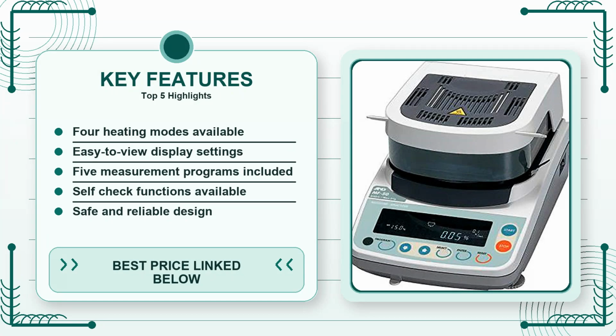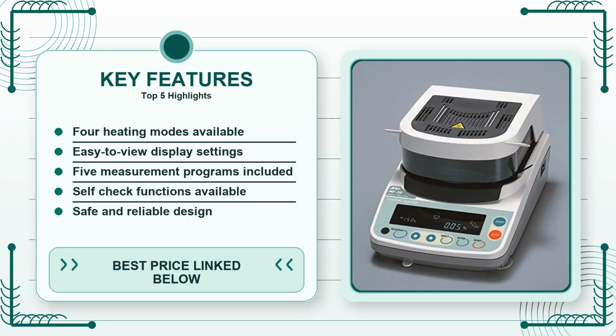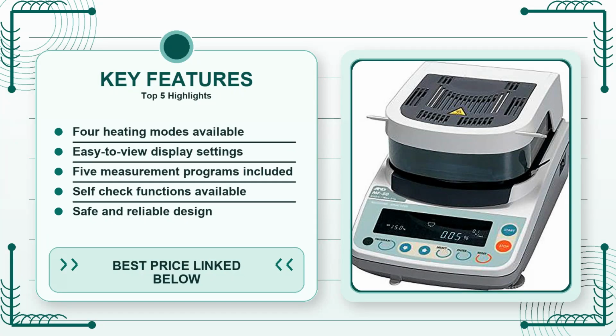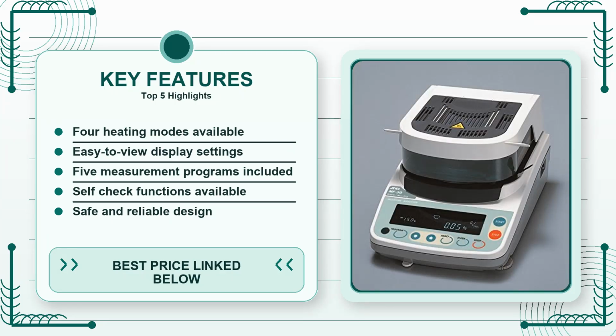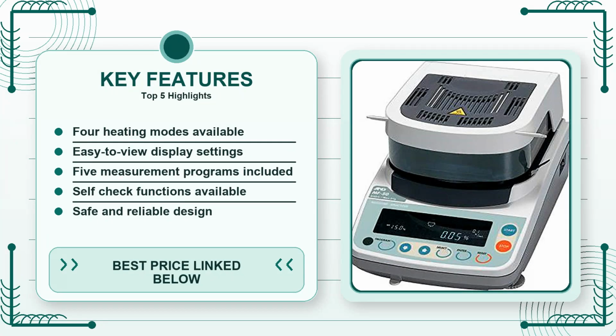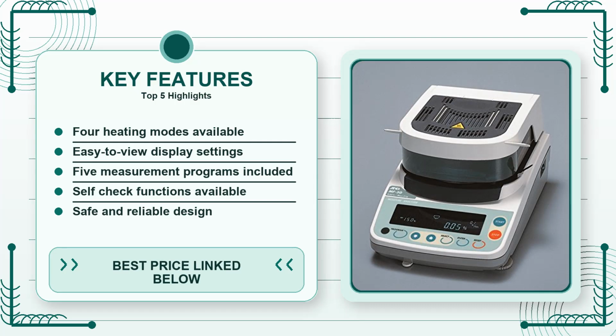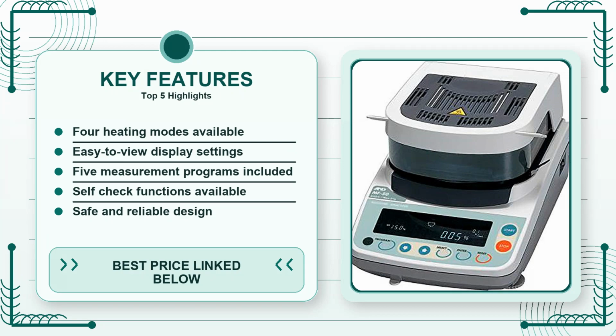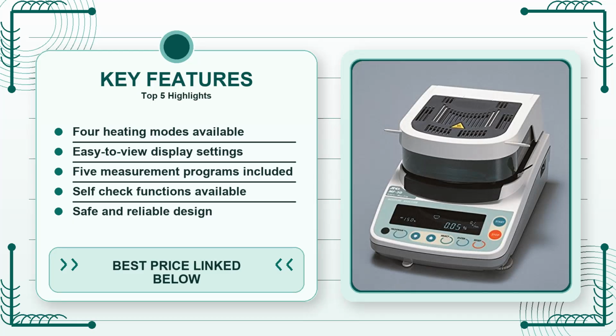The balance's maximum capacity is 51 g, which is fine for most powdered samples but limits you if you ever need to test larger bulk materials like a handful of dried herbs or a chunk of polymer. The 0.001 g readability is impressive, yet it can feel a bit finicky if your sample's moisture loss is in the range of a few milligrams. You might end up chasing noise rather than meaningful data. The unit also doesn't have a built-in data logger, so you have to manually record the final moisture percentage or export it via the optional USB cable, which adds an extra step if you're trying to keep a digital lab notebook. Finally, the safe and reliable design is a plus, but it also means the housing is fairly robust and a bit heavier than a typical benchtop scale, so moving it between labs isn't as painless as you might hope.